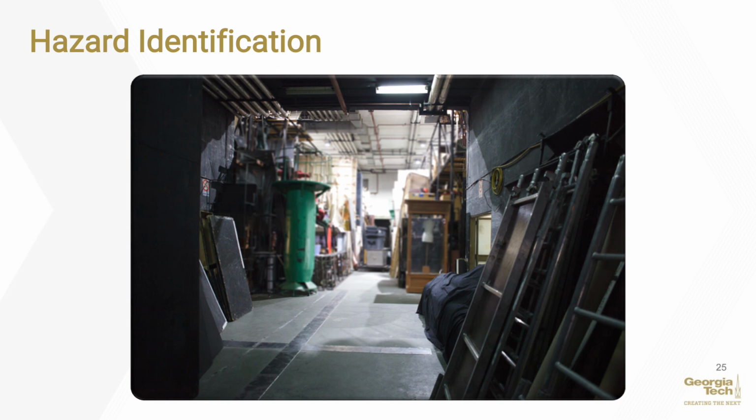Answers include: when preparing your emergency action plan, designate primary and secondary evacuation routes and exits. To the extent possible under the conditions, ensure that evacuation routes and emergency exits meet the following conditions: clearly marked and well lit, wide enough to accommodate the number of evacuating personnel, unobstructed and clear of debris at all times, and unlikely to expose evacuating personnel to additional hazards.